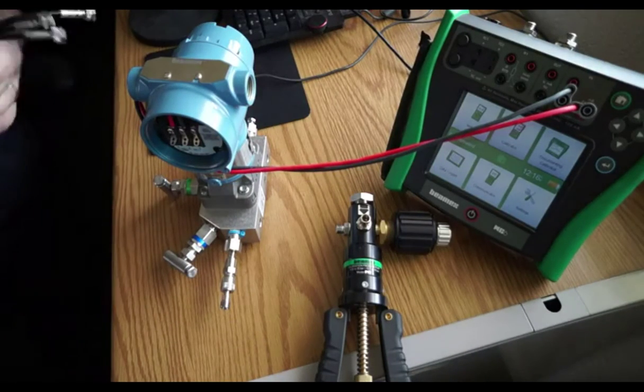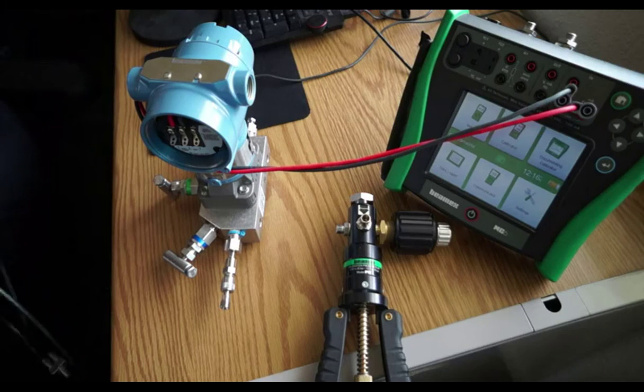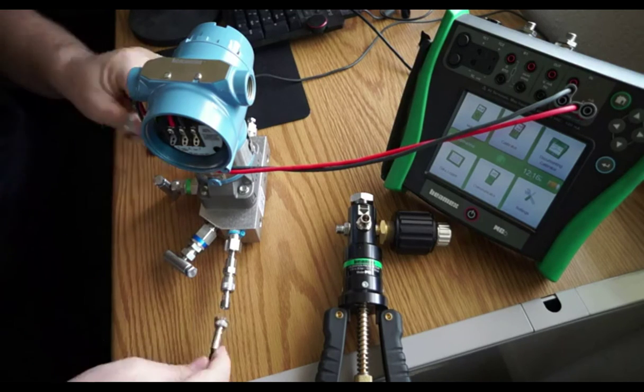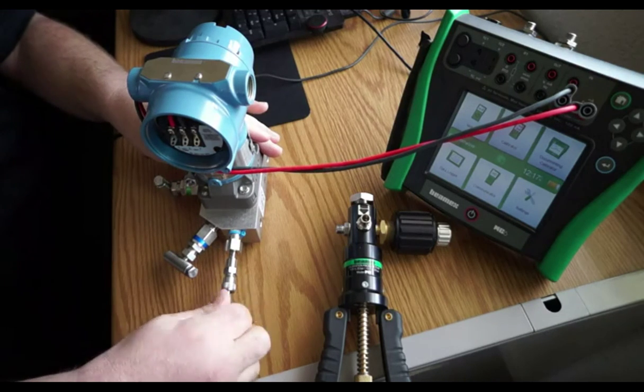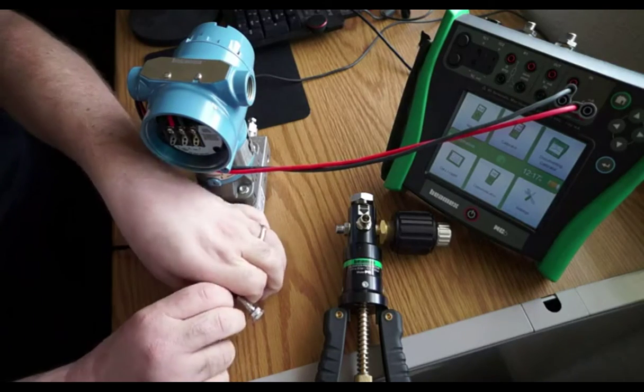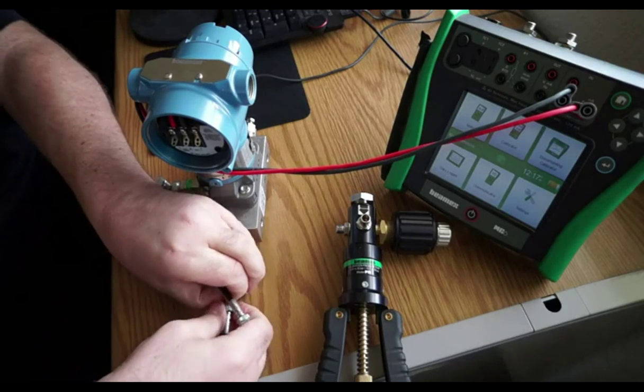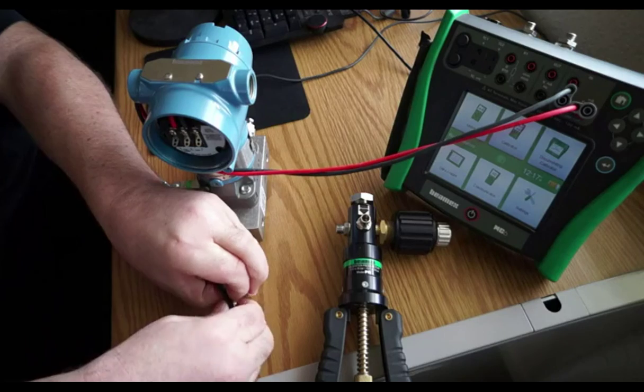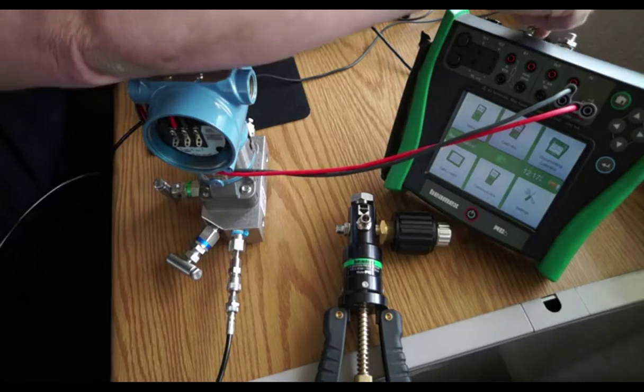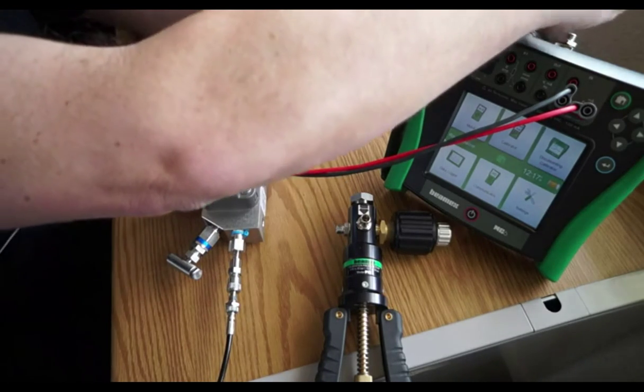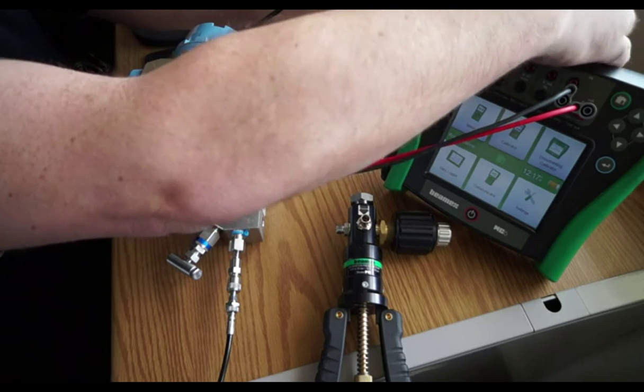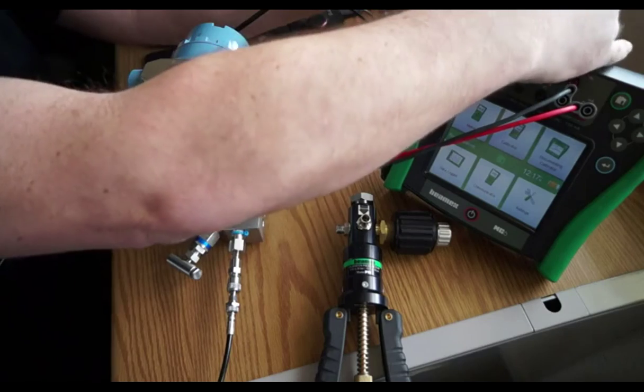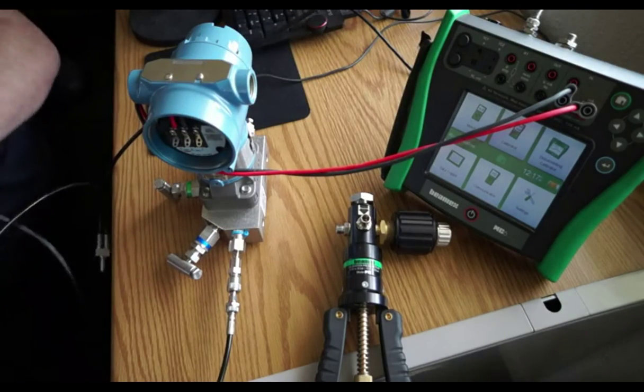So now we have our 3 connections. We'll take one connection here. These are all designed to be finger tight and not have to use tools on them. I'll do one of them on the transmitter, I'll do one on the calibrator itself, and the final one on the pressure pump.